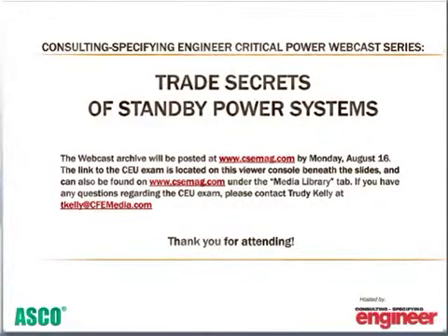The first unit that is up to frequency and voltage transfers to the paralleling bus, and then all the other units will synchronize to that. With today's very accurate digital governors, sometimes it's a little difficult to get the generators to shift enough so that they can come up to the right frequency, because if they don't transfer within about 10 or 15 degrees, you start having some problems and transferring out of phase. But normally, they all transfer fairly quickly once they all come up to speed, and they all start about the same time. So they'll start in about 5 or 6 seconds, 7 seconds, according to how big they are.